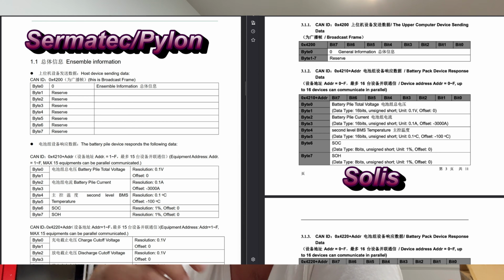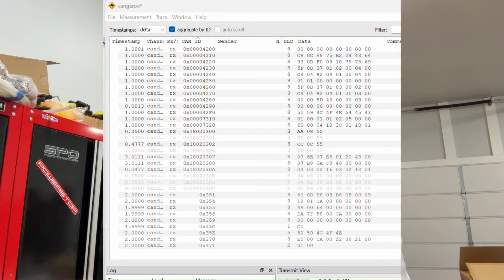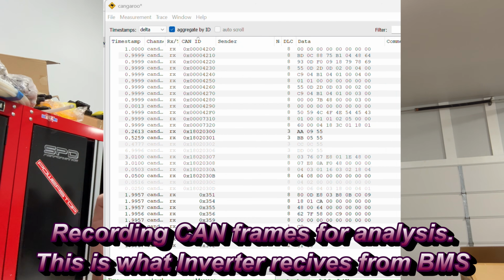Now, here's something a lot of people don't realize, and what I didn't realize a year ago, is that the most often used form of communication is based on the Pylontech protocol, either low voltage or high voltage. They set the standards years ago, and even today most inverter manufacturers, including Solis, use a protocol that's built on top of the Pylontech message structure. So if your BMS can speak Pylontech, chances are it will work with a lot of different inverters.